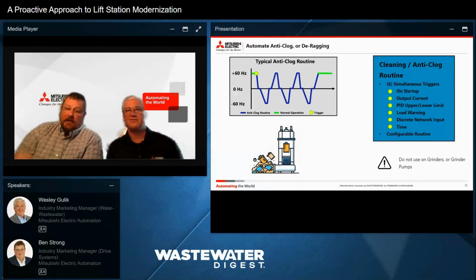Most of these drives, an anti-clog routine is configurable, so you can cause it to oscillate. And what that does is it pulls the fouling or the material and blows it back out the suction, moves it around, dislodges it, so that material can transfer out of the pump. What we recommend to customers is these triggers are ORs. So don't just say, I only want to run an anti-clog routine when I get a load warning. Back to load characteristics: if you set it up and use load characteristic monitoring, then you can trigger this routine on high or low alarm points, right?